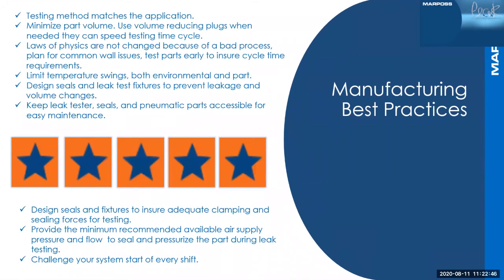Some of the best practices we want to look at: make sure the testing method matches the application. There are some places where you're using large leak rates and differential just doesn't work for it. Minimize part volume. Use volume reducing plugs when needed. They can speed your testing cycle. Laws of physics are not changed because of a bad process.